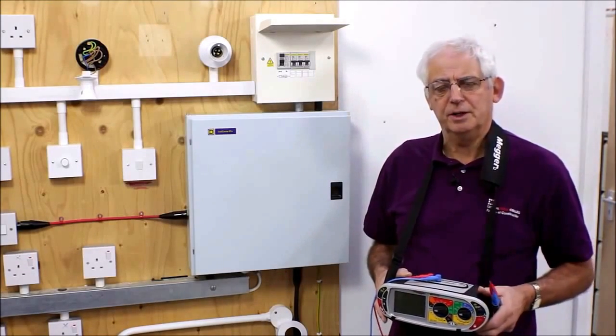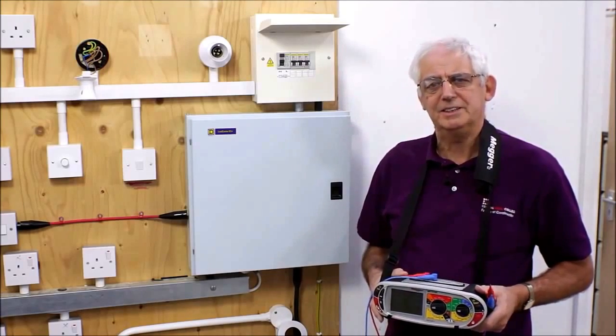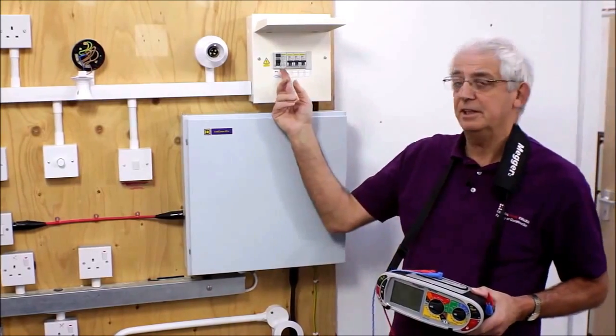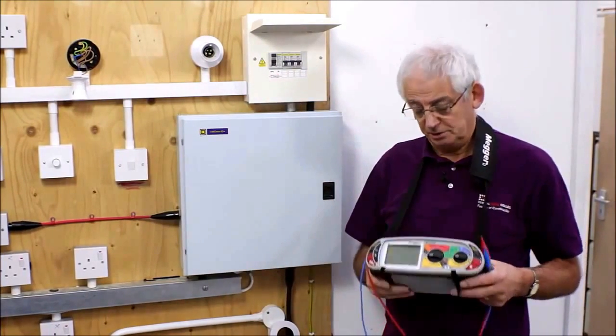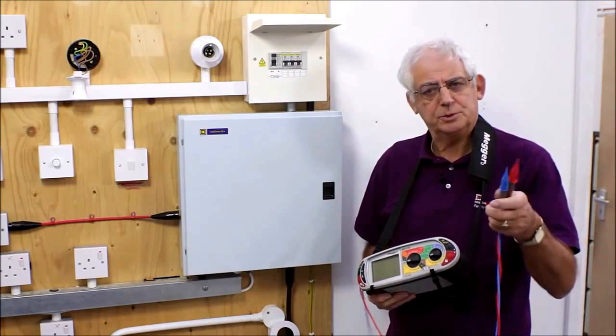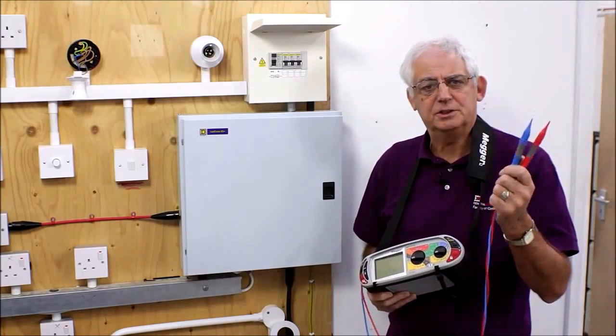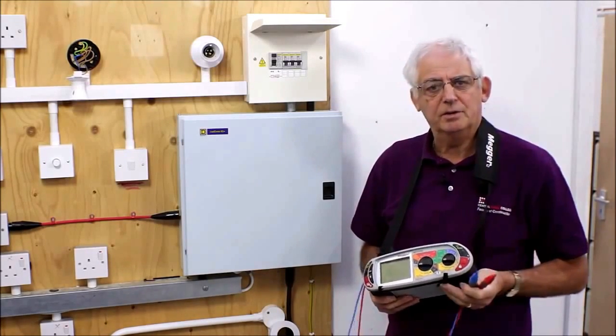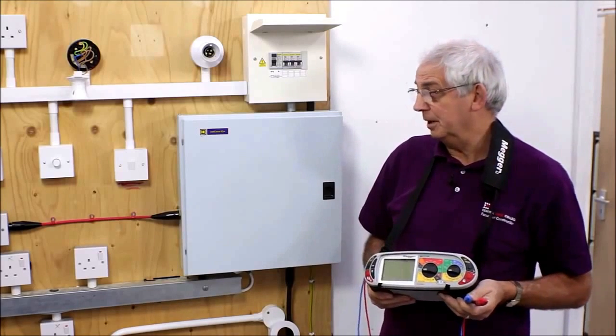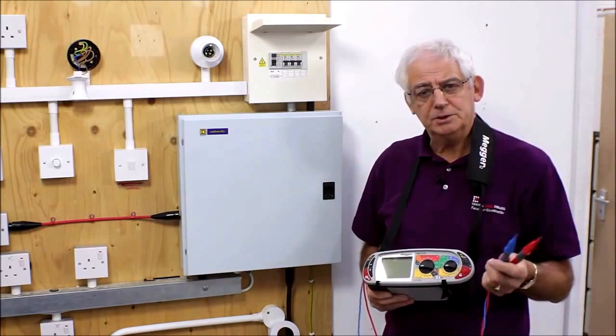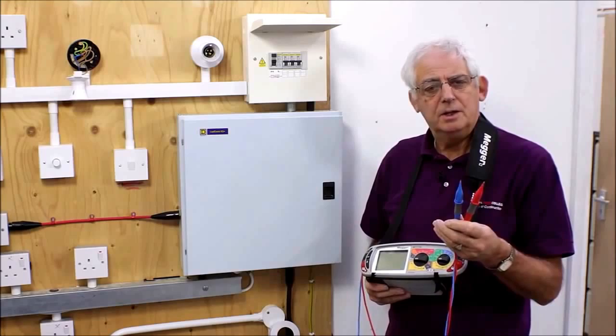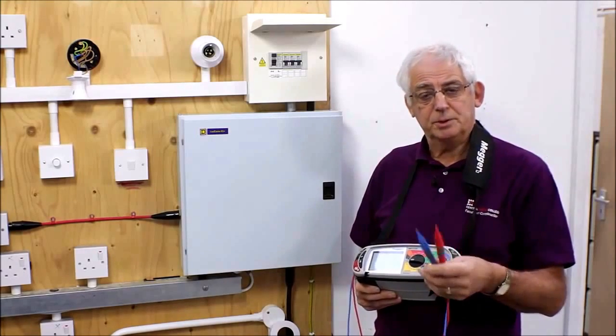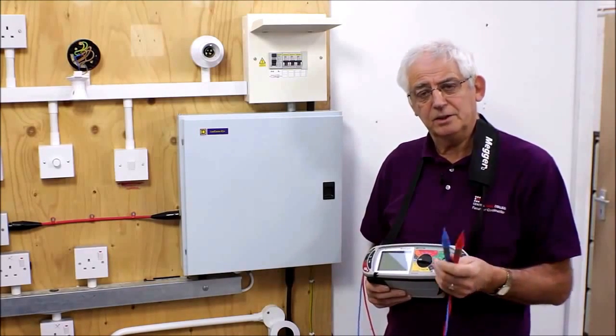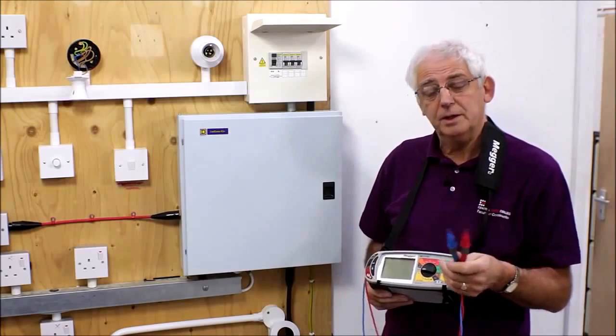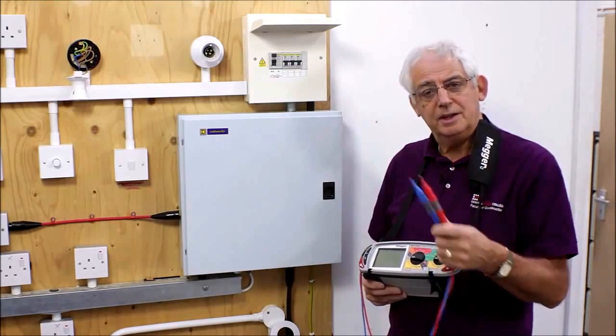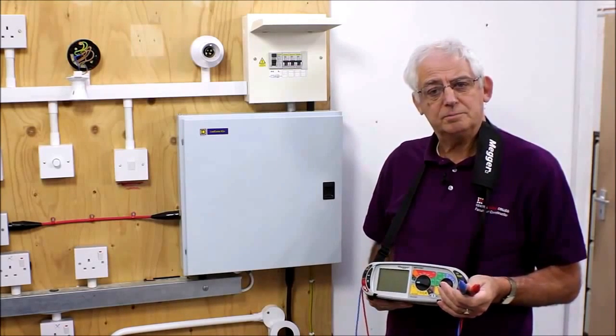There's several ways of doing it, but the ideal way and the easiest way, particularly if there's an RCD in the circuit, is to use a test instrument which will allow you to take the test using 2 leads and a very low current so that it doesn't trip the RCD. You have 2 options using this type of instrument. One, you can do it at the switch between the switch line and the earth, or you can do it at the lighting point between the switch line and the earth as well.